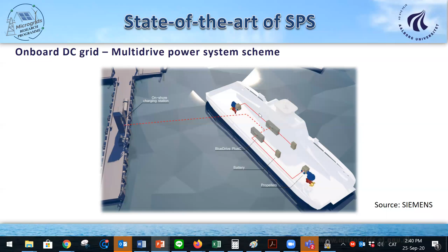And then, of course, ABB comes with another idea. It's the same DC microgrid system, but in that case, in order to reduce losses, the converters are embedded with the motors, so they are close to each other in the same box. The good thing about that is that you reduce the distribution losses. However, you can see the DC connections are still, let's say, far away, so you don't have a box anymore, you have long lines. This means you have to increase the voltage a lot, and if you increase the voltage, protections become more difficult in DC.